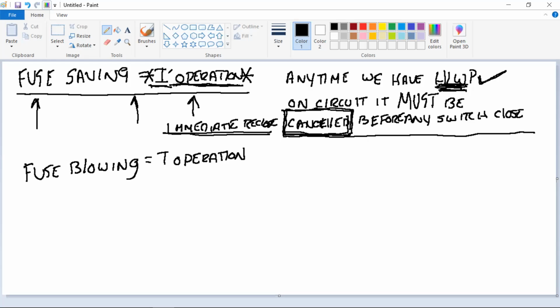Okay. And this is the point we're getting to right here. As soon as you have the instantaneous open and reclose, the fuse is going to blow. And normally, if it's a good fault, you are not going to go to timed. You're going to give that fuse just enough time to blow before you get to the next timed operation.